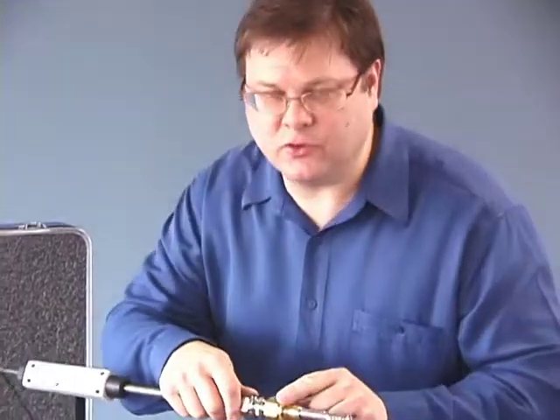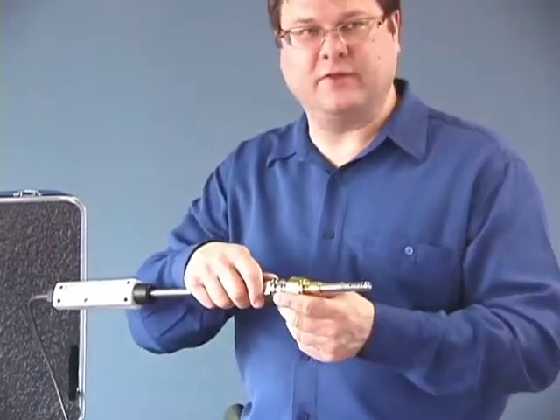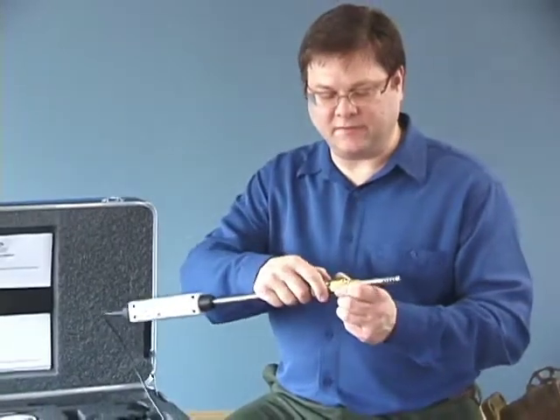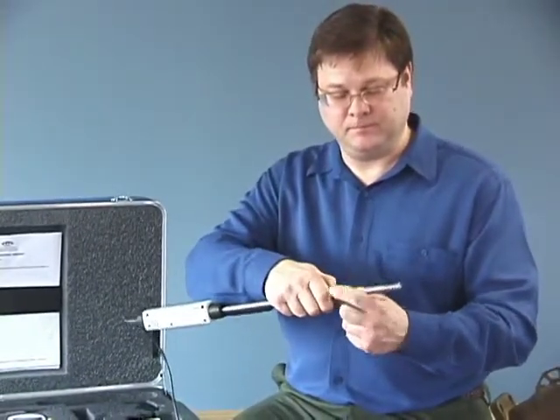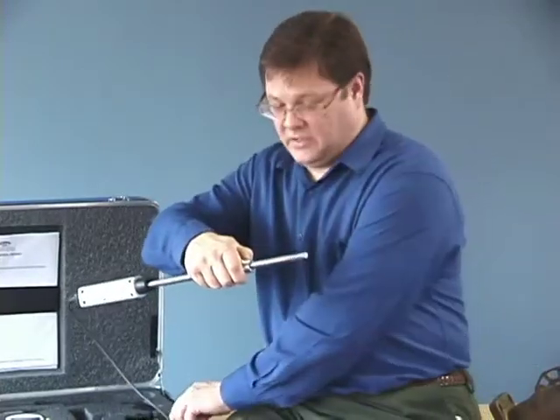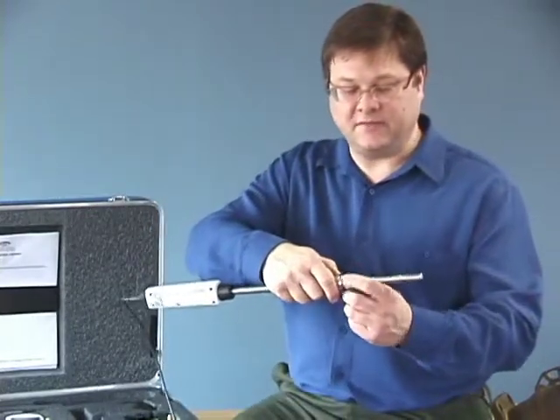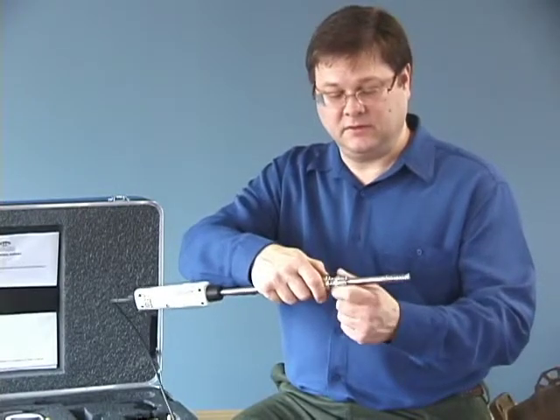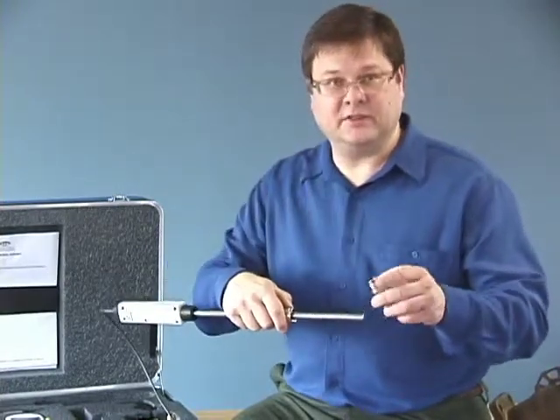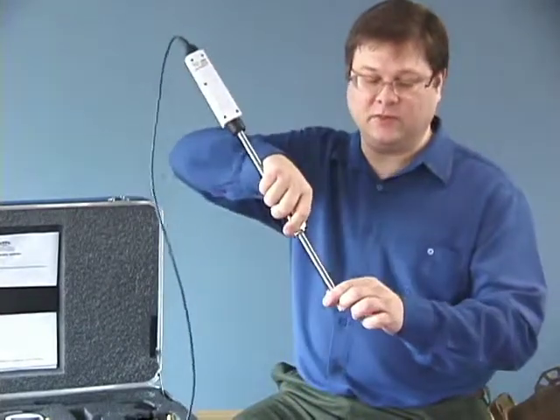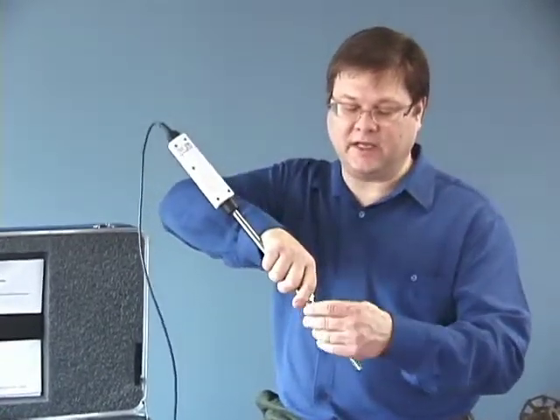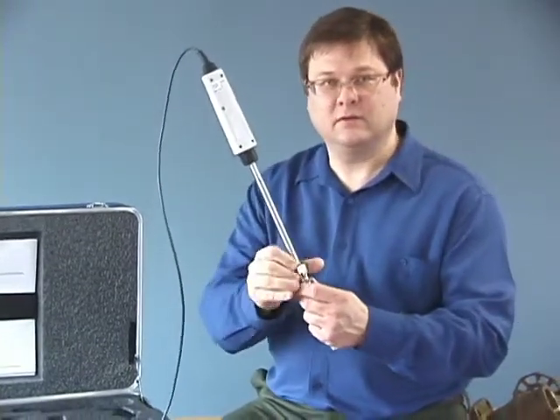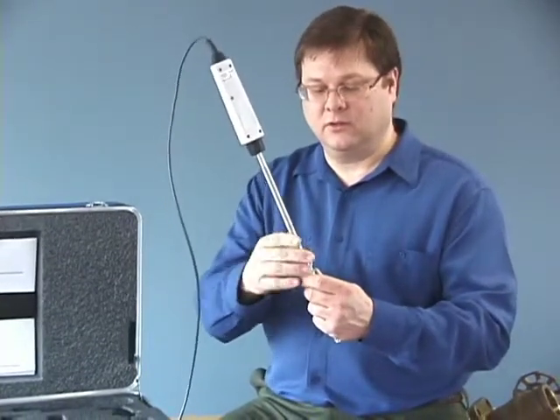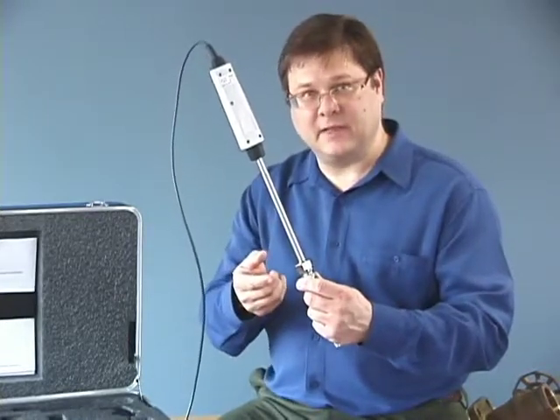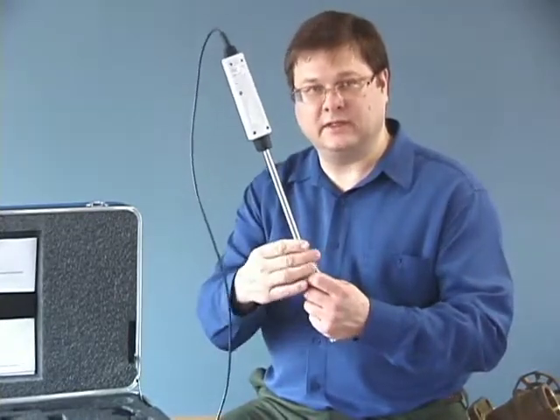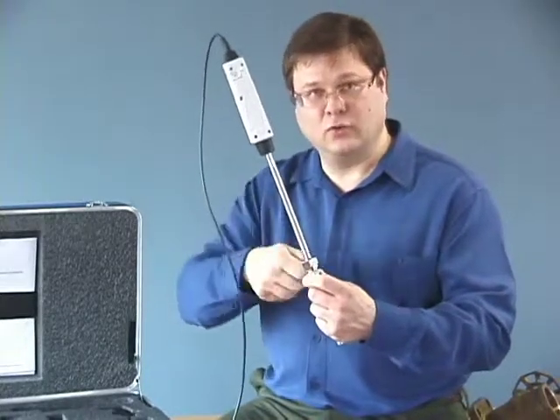In addition, you can use the quick connect fitting to mount it into a drain valve, but you don't have to. You can take the quick connect fitting off, it slides right off like that, and then you can take the fitting body off and mount it to any valve. Then you put the sensor in, you open the valve, push the sensor down, close your fitting. You're going to let any gas escape until you get oil coming out, and then you're going to hand tighten it, and then quarter turn.